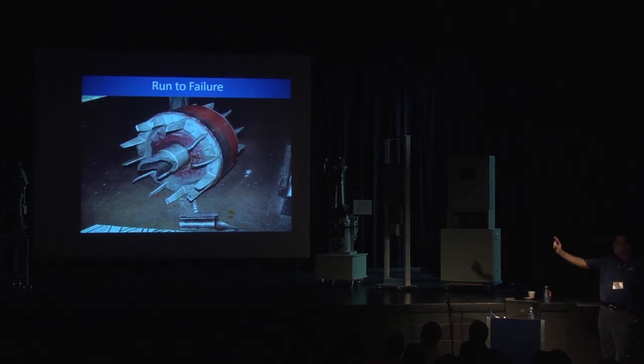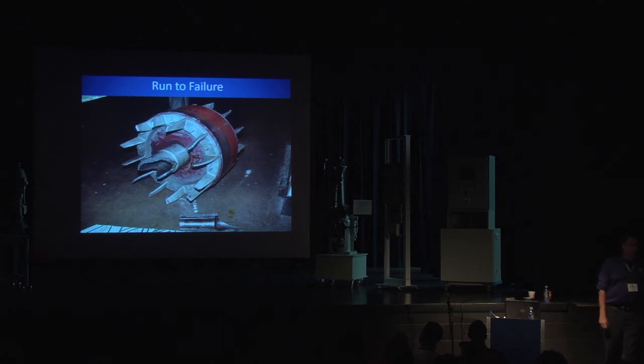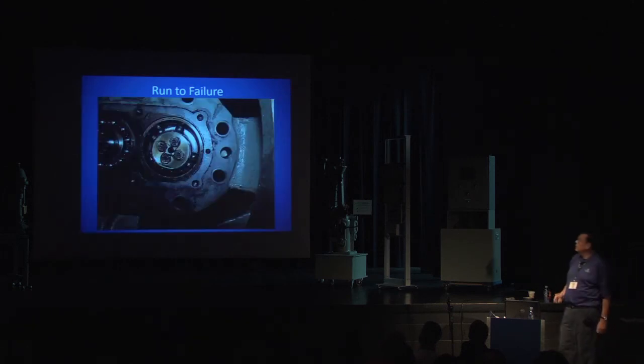I don't know where I got this picture, but if it costs $1,000 in parts and labor to replace bearings, versus a failure on one of the old oil pumps nobody makes anymore, costing $100,000 to replace the Governor oil pump, you haven't really saved anything. You could replace those bearings maybe 100 times for what it would cost to replace the pump. I could go on and on about run to failure.